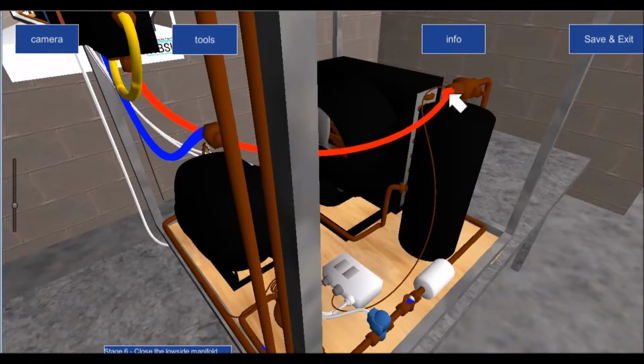But we want to prevent or minimize the amount of refrigerant that we let out. So we have to remember that it's only a slight purge that's needed, because the quantity of air that we would have is going to be heavier than the refrigerant, so it's being pushed by the refrigerant. It's going to sit on top of the refrigerant. So, sorry, it's not heavier. It's lighter than the refrigerant, but it's going to sit on top of the refrigerant, and it's being pushed by the refrigerant out the hose line.